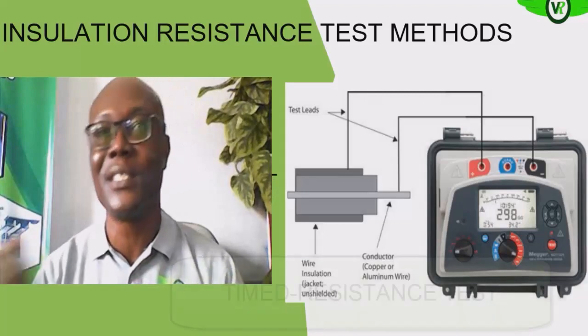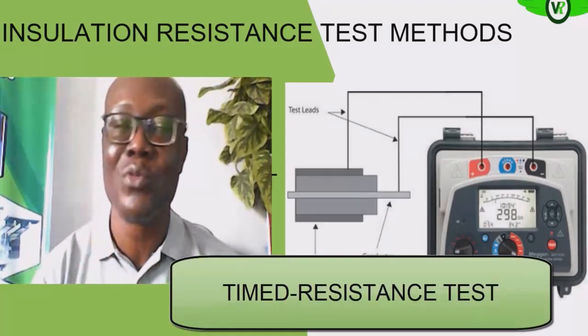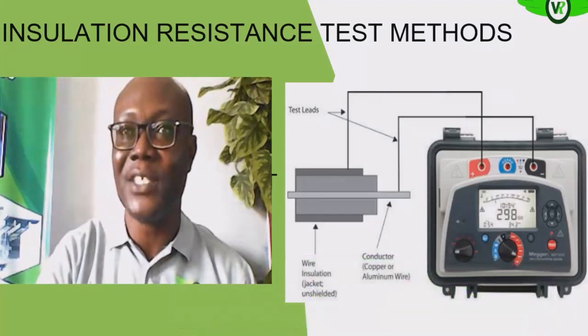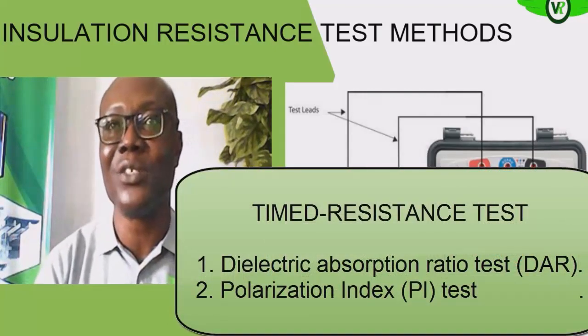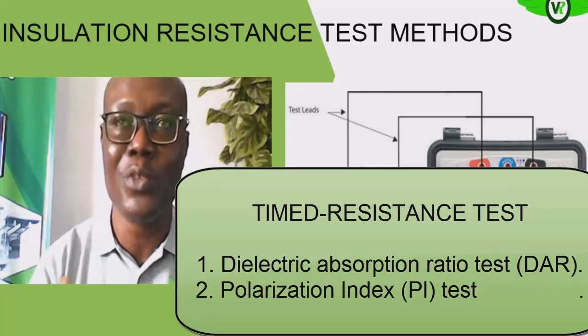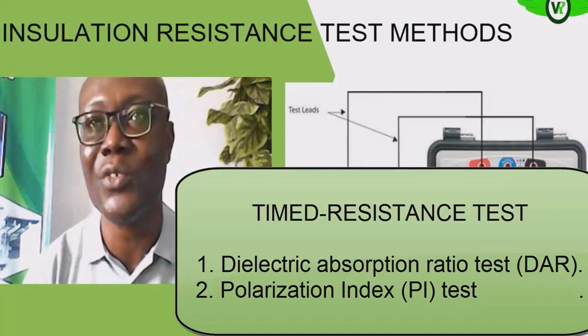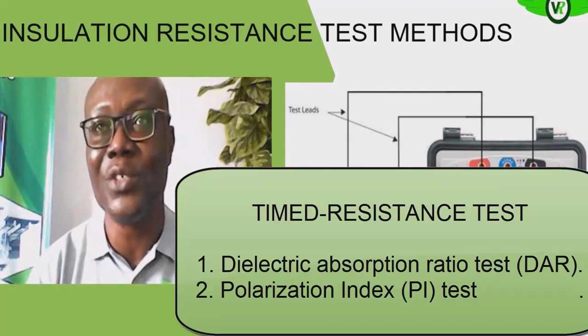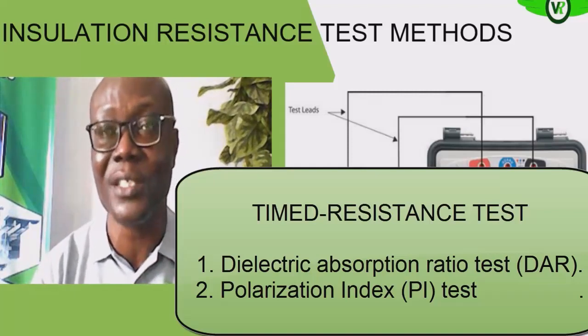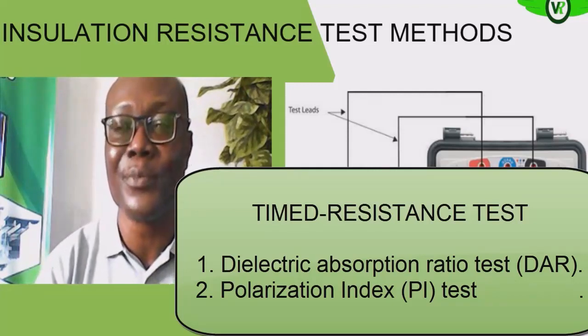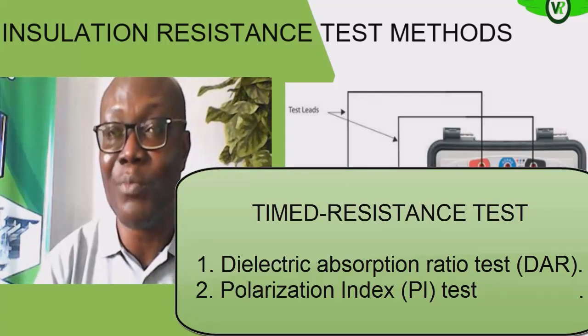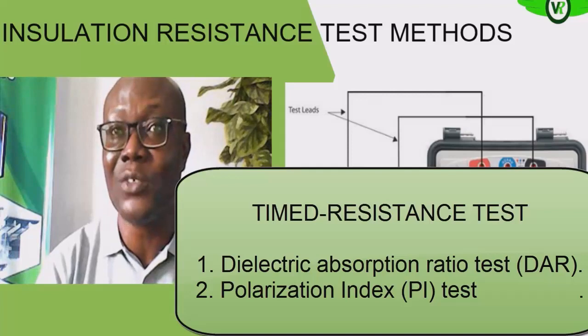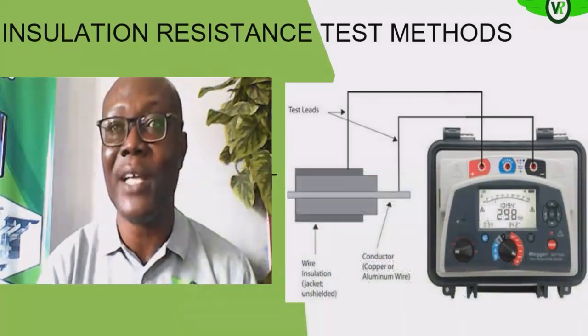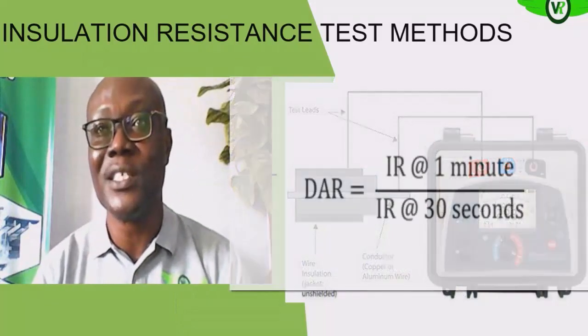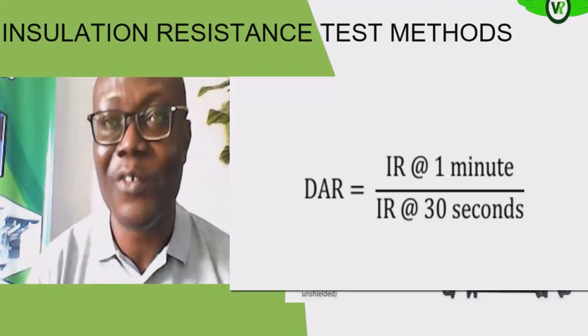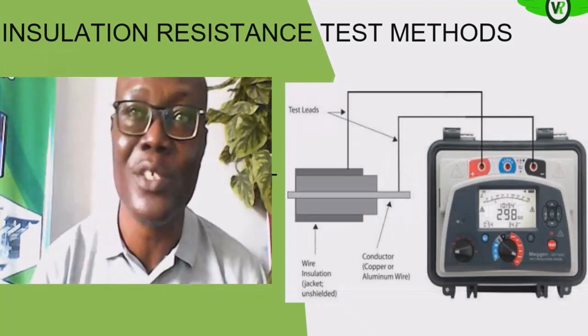Then the other one is the time resistance test. Under the time resistance test, we have two basic test methods. We have the dielectric absorption ratio test, and then we have the polarization index test. Both of them are a step further than the spot reading. So the dielectric absorption ratio test is, as the name implies, a ratio test. You take the insulation reading of whatever insulation you are testing at 1 minute and divide it by the reading at 30 seconds or 20 seconds, as the case may be, depending on what your facility approves. But either of them will give you a good result.